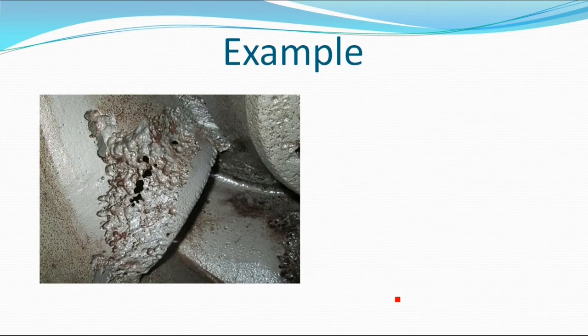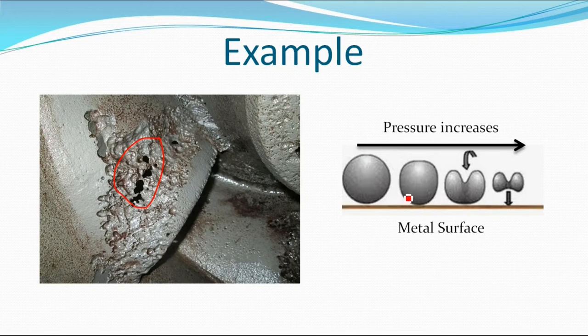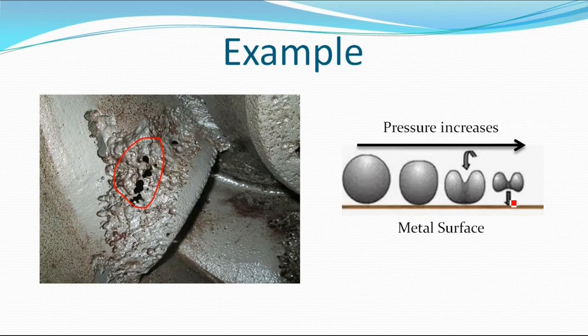This picture shows the real result of cavitation — you can see how the surface of this impeller is eroded because of cavitation. This did not happen in a few days; it took a long time because of repeated cavitation. In this image, you can see the bubble as it moves to a higher pressure region — it collapses. In the lower pressure zone it is fully intact, but as it moves to higher pressure it decreases in size, and the liquid in the higher pressure area presses and compresses it until it collapses. A shock wave is then transferred to the metal surface, removing a small chip and causing erosion. That's how cavitation leads to damage of parts.